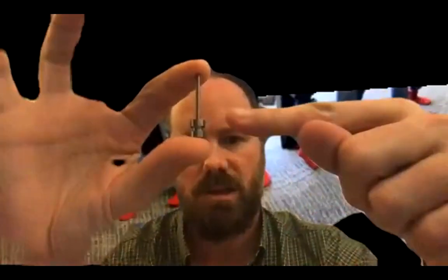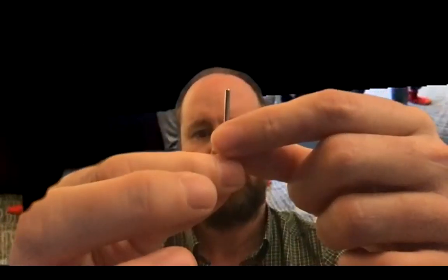Let me answer a couple of other questions that were asked, some of them privately. There was some interest in the thermistor housings. This is our standard thermistor housing. This part at the bottom we call the boss, and this goes into the instrument. The thermistor itself is inserted through the hole in the bottom, and goes up to the top. Ben, you were asking about the size of it. You can see it on the camera, and I'm holding it here. So this thermistor inserts inside. Sorry about my background effects, which are probably causing confusion.